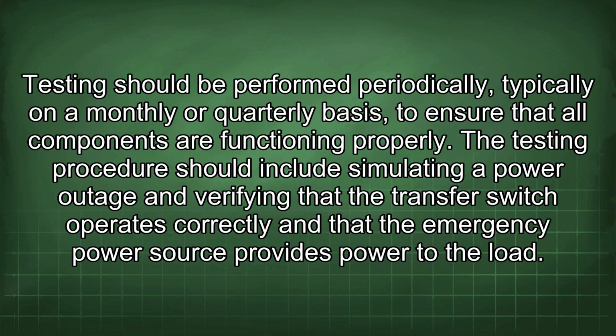Testing should be performed periodically, typically on a monthly or quarterly basis, to ensure that all components are functioning properly. The testing procedure should include simulating a power outage and verifying that the transfer switch operates correctly and that the emergency power source provides power to the load.